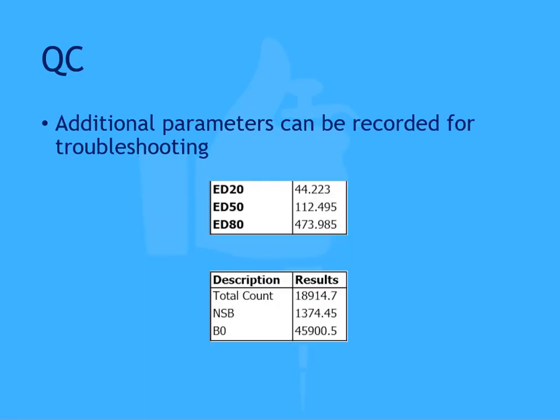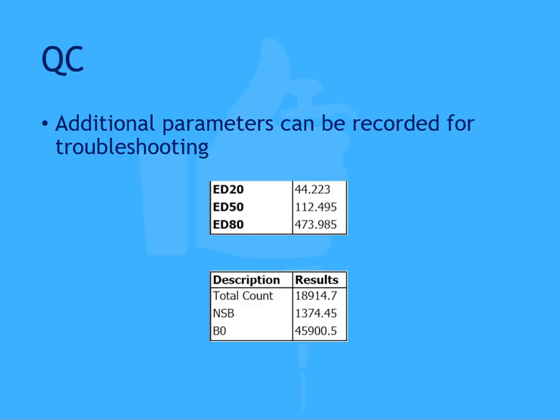You may also decide to record other parameters like the ED20, 50, and 80, the total count, NSB, and B0 CPMs. These parameters could be used in a troubleshooting capacity as opposed to for assay validation. For example, if you have a string of run failures and you notice a significant negative bias in the total count CPMs, it could be indicative of a premature degradation of the tracer reagent. This could prompt investigation into kit storage.